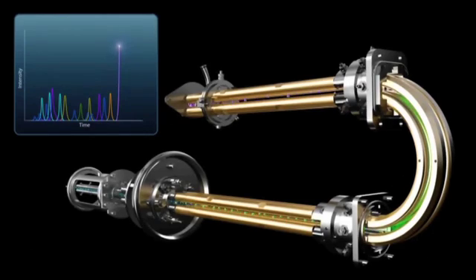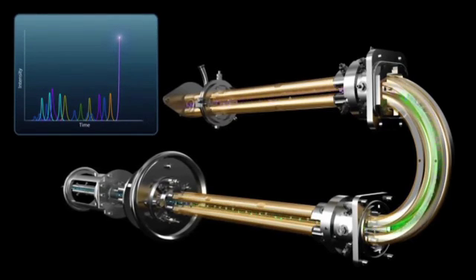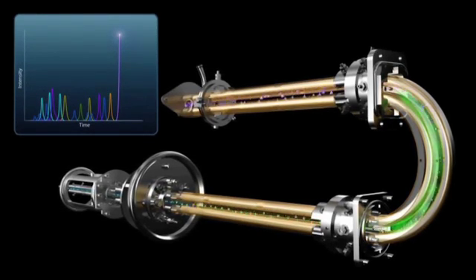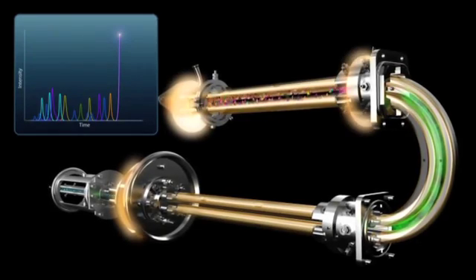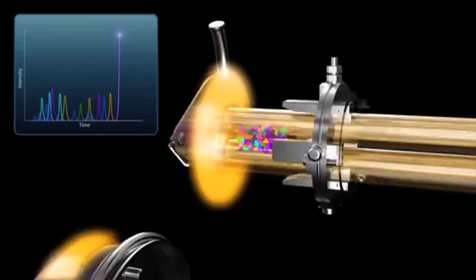But uniquely, when a specific MRM transition is detected, Q3 can automatically switch to linear ion trap mode in less than 1 millisecond to deliver high-sensitivity full-scan MS-MS data.